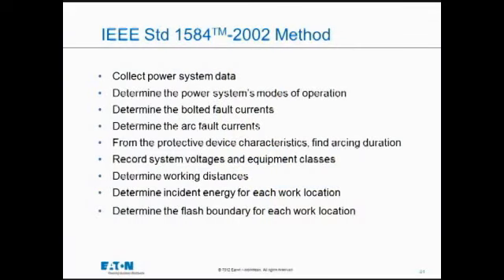How to do an arc flash study is listed on this slide, more or less the basic points. The most time-consuming and hardest part is the first bullet point. What have we got to deal with? What is the lay of the land? What does our power system look like in terms of cable runs, size of conductors? How are they run in conduit or in a cable tray? Is there 2 per phase? Are they in a metal conduit or a non-metal conduit? That's the cable side, and then the rest of it deals with the other devices in the system, transformers and motors and generators and utility connections. All of that data has to be gathered along with the timing information. Circuit breakers and fuses. What type of circuit breaker and setting do we have in terms of time? What type of fuse and size of fuse do we have for the same thing, for timing?